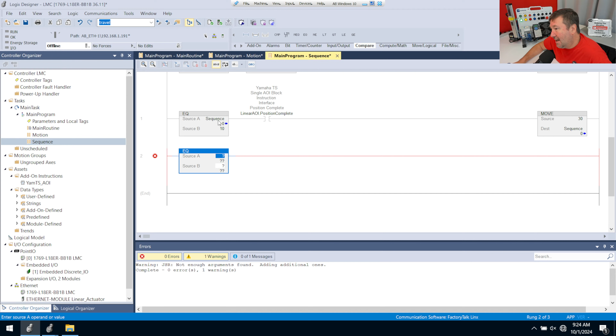Okay, so once we're at 30, then we want to bring a rung down. We want to go back to 0, because all we're going to do is zigzag back and forth between 300 millimeter and 0 millimeter. And so we'll go ahead and bring an EQU, or I'm sorry, in 36's case, it's called an EQ instruction down. And yours, it's an EQU if you're before 36. And we're going to look for that sequence to be equal.